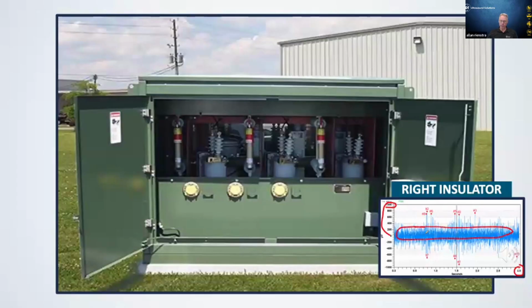Now, what's important to keep in mind is what we call the inverse distance law. The inverse distance law says that if I double the distance that I am away from the defect, then the signal is going to halve itself. And if I halve the distance, then the signal is going to double itself. For consistency's sake, all that means is that if I'm scanning this one, and then this one, and then this one, the distance that I'm standing away from them needs to be uniform for the 3 time waveforms and the signals to be comparable.